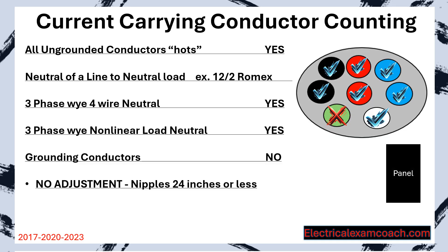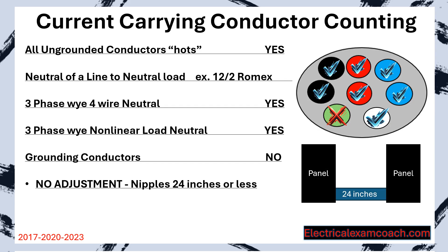No adjustment will be made for nipples that are 24 inches or less. Let's imagine we have a panel on each side and we want to run a short nipple that's 24 inches or less — this does not count in our bundling adjustment, which is a thing of beauty, because otherwise you'd have to de-rate all conductors jumping just 12-gauge circuits from a house panel over to a generator.